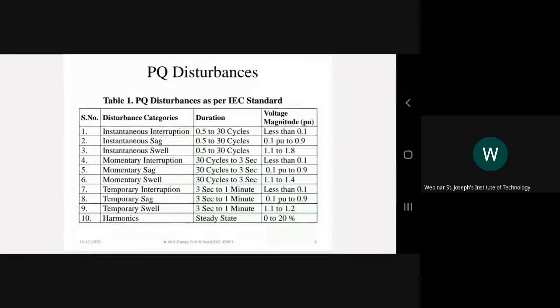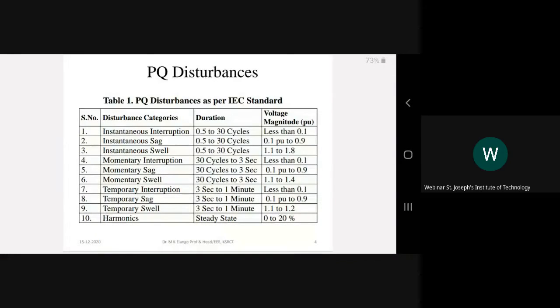And for temporary interruption, the problem exists from 3 seconds to 1 minute. These problems are classified as temporary, right? So as per the IEC standard, power quality problems are classified mainly into the following categories: instantaneous interruption, sag, and swell; momentary interruption, sag, and swell; temporary interruption, sag, and swell; and finally harmonics. For harmonics, the duration is steady state, right?